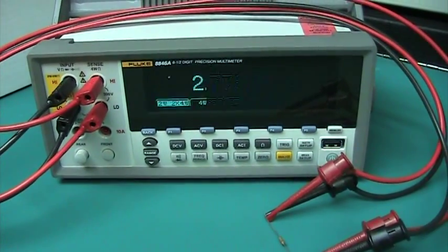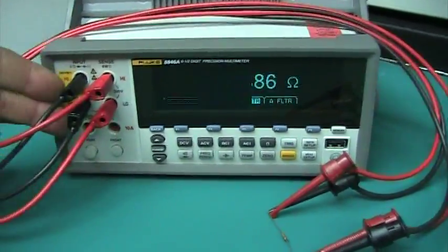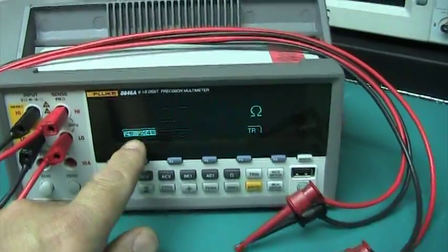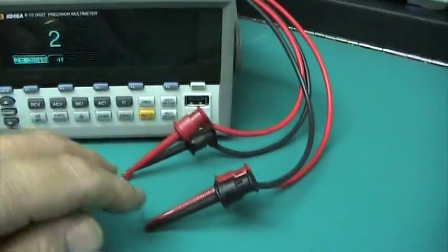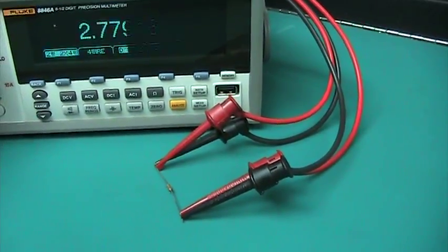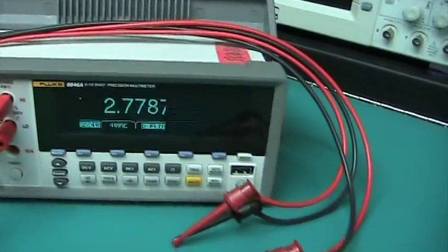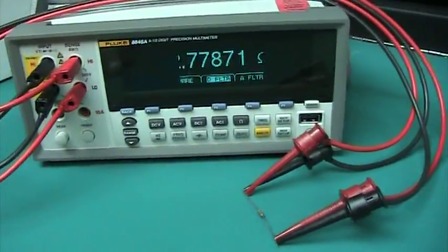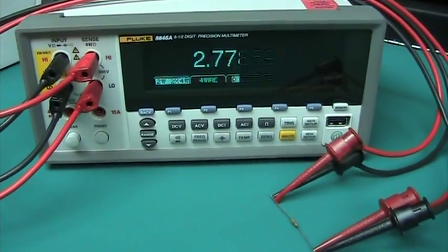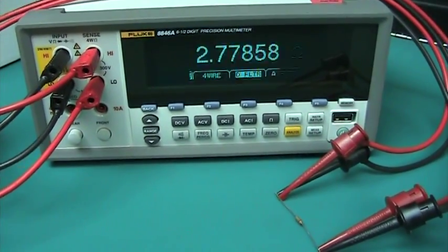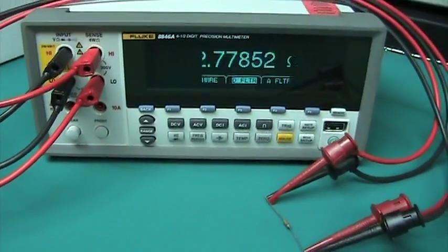Four-wire ohms measurement versus two-wire, what does that mean? Two-wire, if we look at the normal leads here, the two black leads on the sides. Right now I'm set in two-wire, so the meter is sourcing current through these to the resistor and also sensing the voltage across there right at the terminals. The problem is the resistance of the leads is included in that measurement because it's measuring back here at the meter. That only becomes important when you're talking about low-level measurements, because typically the lead resistances are small, but when you get down into ten ohms or less, all of a sudden that lead resistance matters.